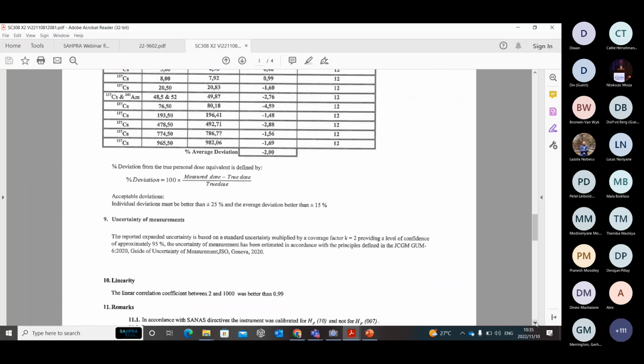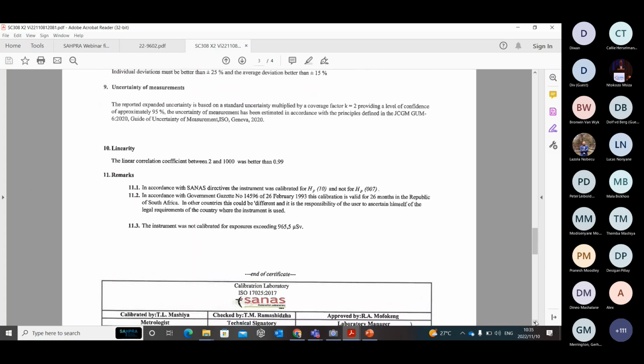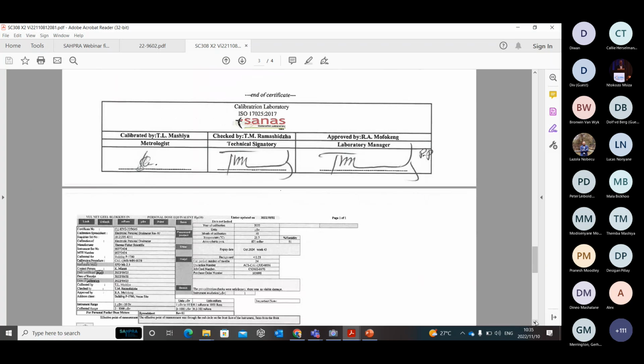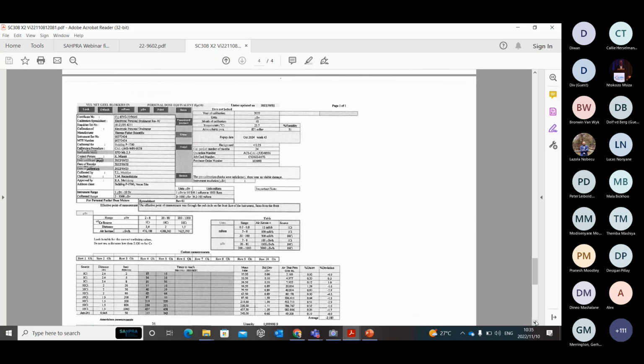Here is the formula below: your percentage deviation is the measured dose minus the true dose, divided by the true dose, multiplied by 100. That is what determines this. It is also clearly stated that individual deviation must be better than plus or minus 25 for a single point of measurement, and for the average it is plus or minus 15. That is what I was saying. And this is our uncertainty, which we state according to the GUM. Let's go to the next page. From here, those are the remarks and also the calibration frequency. Now this is the raw data.